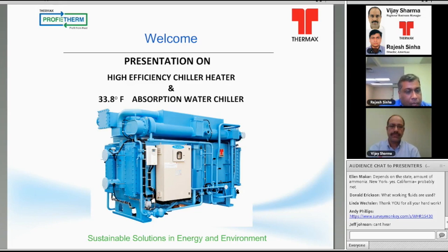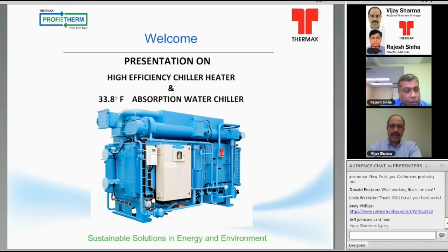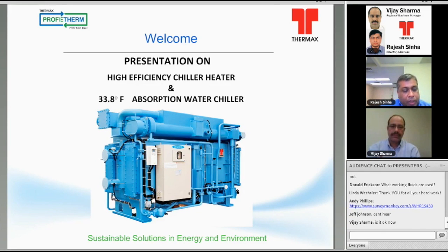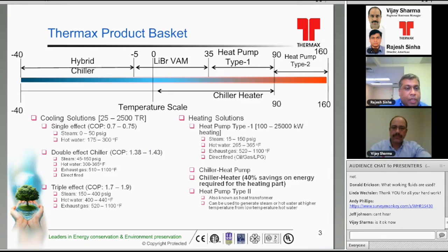So essentially, the technology is largely the same as what has been used in the past, but we have made several innovations around the technology in terms of range expansion, type of heat utilization, and the lower end of the temperatures, being the chilled water temperatures, which could be established. Currently, one of the primary highlights of this presentation is how we are generating 33.8 degree Fahrenheit chilled water temperatures using this technology.